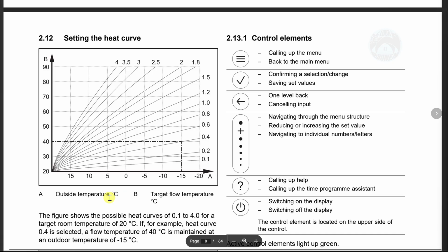As mentioned earlier, I was testing room temp mod set to inactive mode. And as much as I love the idea of relying solely on the weather compensation to determine the current flow temperature, this mode is not ideal for a number of reasons. The main reason is if you don't know which heat curve you're meant to be on.